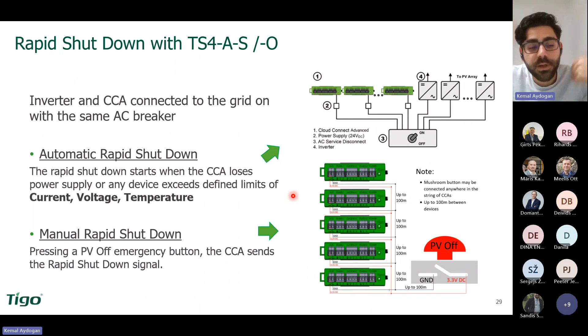Let me show you here. See on the right-hand side, there's an AUX port. If you short this AUX port, you are going to have 0 volts here, and you're going to send each optimizer to stay in rapid shutdown mode. If you release the button, then you're going to reopen the circuit, and you're going to have 3.3 volts. That means all the optimizers are receiving the signal to stay on mode.